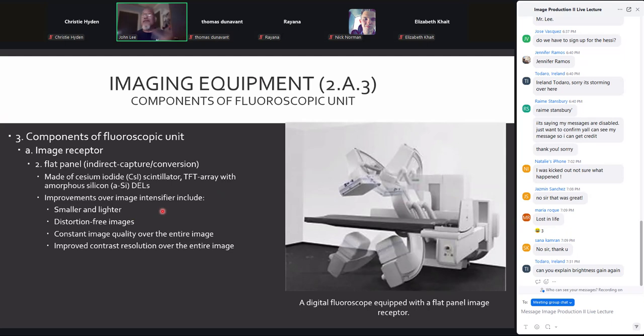The improvements over the image intensifier: they're smaller, lighter, they take up less real estate. The images are square or rectangular, as opposed to round. They have no distortion in them. We get a consistent image quality over the whole thing, as opposed to the image intensifier, which makes it a little bit brighter, and then it just kind of vignettes as we get towards the edges. That means it dims. We get improved contrast resolution as well, because now that light is going directly into a specific address that corresponds to a specific pixel address in our image.